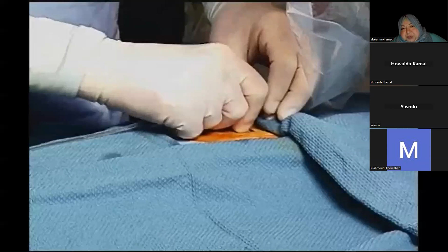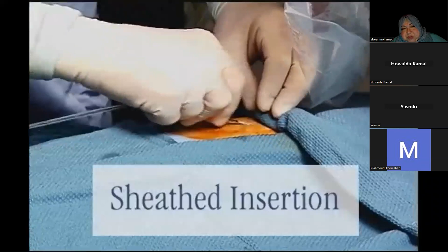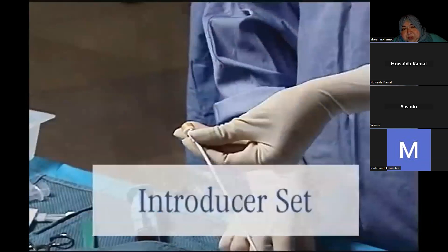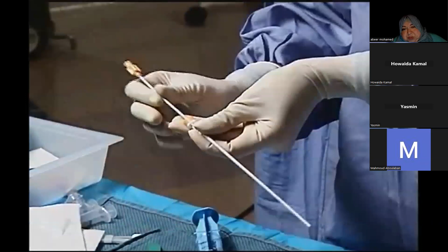If fluoroscopy has not been used to guide balloon placement, an X-ray must be taken immediately to confirm correct balloon positioning. If you are unable to advance the balloon without the sheath, remove the balloon, leaving the guide wire in the patient, and proceed with sheathed insertion. Assemble the introducer set by inserting the dilator through the hemostasis valve into the sheath. The hemostasis valve houses a diaphragm that minimizes bleeding while allowing passage of the dilator and balloon catheter.